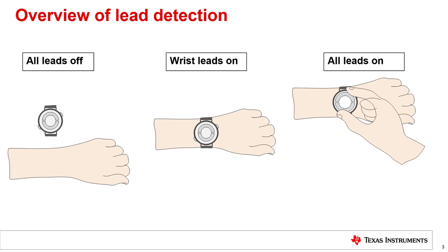On the other hand, whenever an all-leads-on configuration is detected, the ECG signal chain can be powered on and ECG signal acquisition can be started. In addition to determining leads-on and leads-off configurations, it might also be useful to determine the strength of the contact to the leads. Such a determination could, for example, be used to alert the user to make better contact to the electrodes.